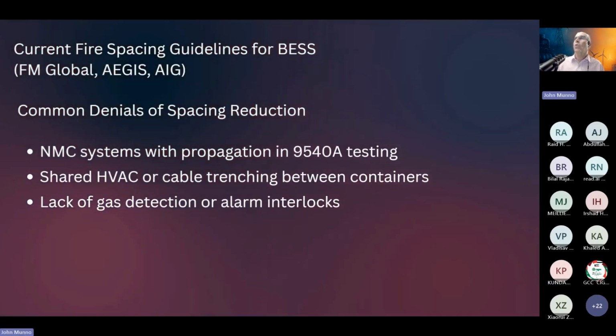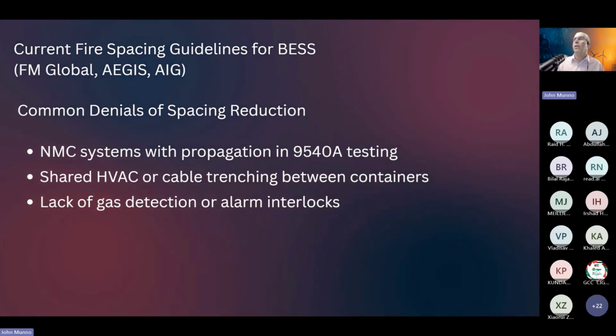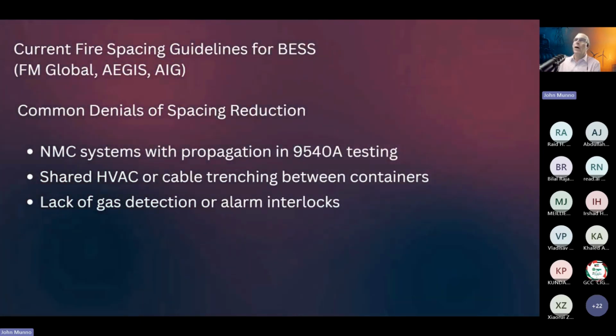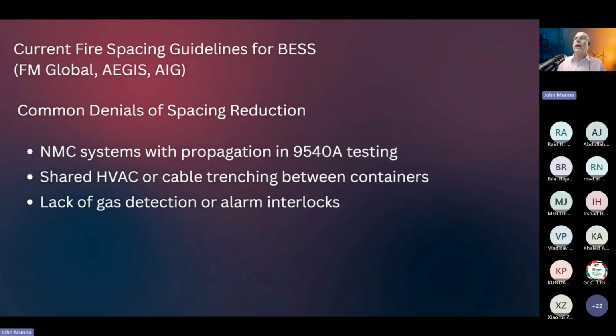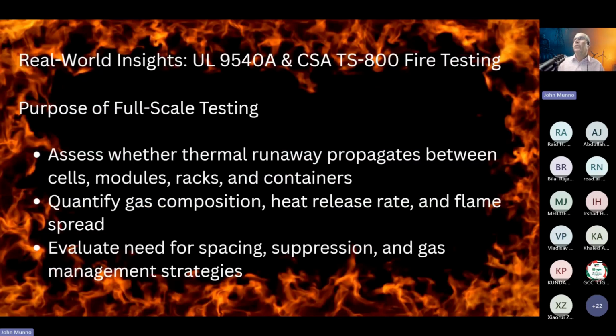So what can go wrong with your spacing reduction? What can drive it towards not being accepted? Well, nickel, manganese, cobalt systems that don't have a good 9540A test, or if you've got shared HVAC or cable trenching that can cause the fire to go from one container to another. And then lack of gas detection or alarm interlocks.